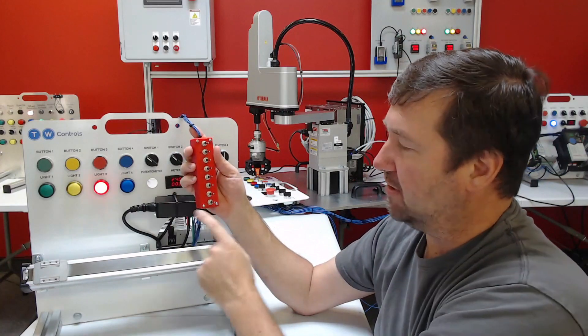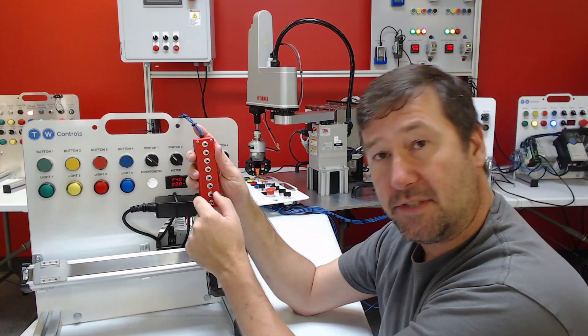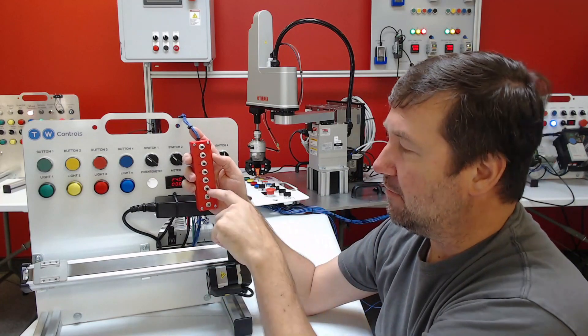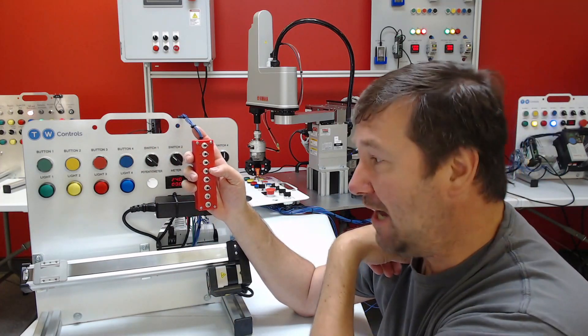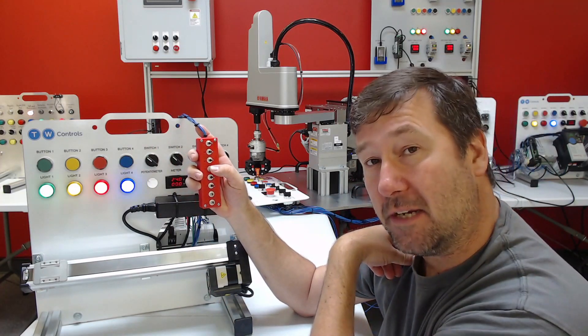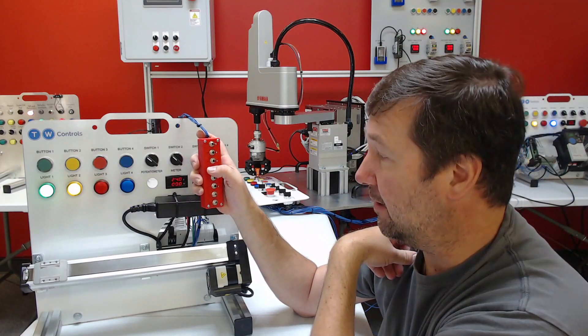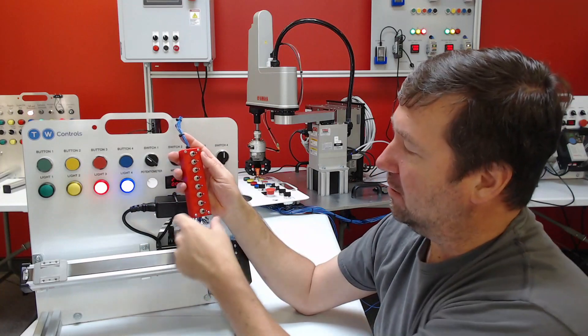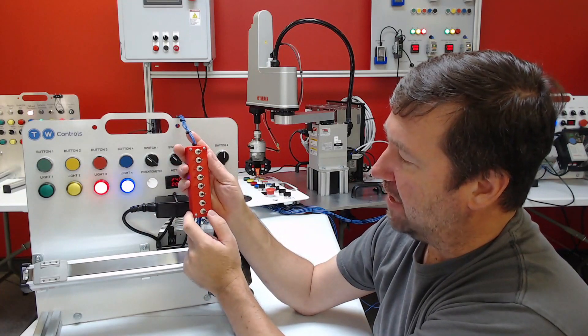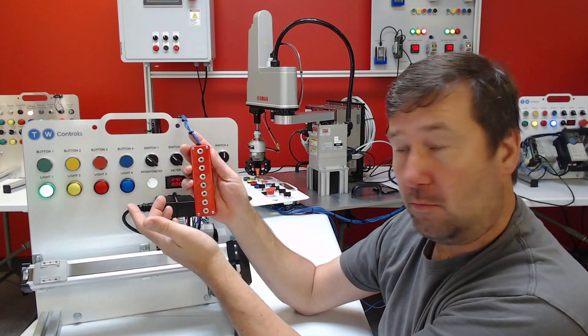Now let's go on through another scenario. Let's say that our low float is good. And we have our stop float. Now for some reason these lead and lag either they get tangled or they both happen to be bad. When you switch the high float on, it should kick both pumps on. And you switch it off. It will keep going until we hit the stop float. So absolutely positively to run, we must have our low float on and our stop float on. And then our lead float will turn on one. And it'll alternate each time.